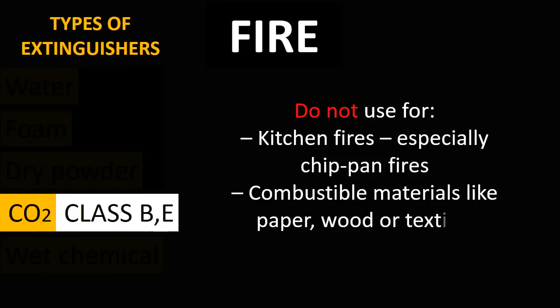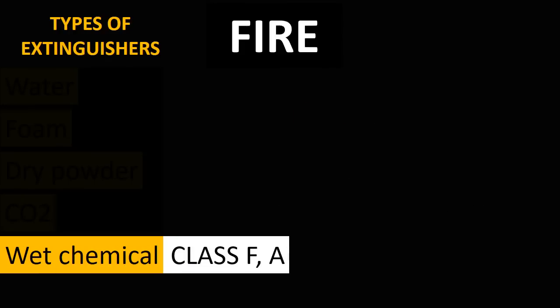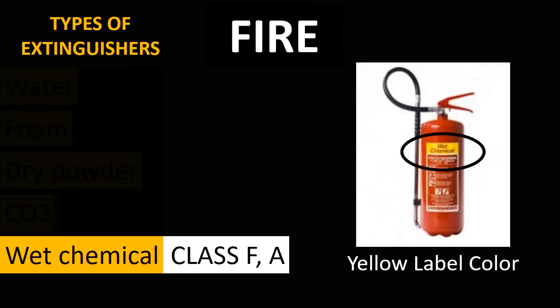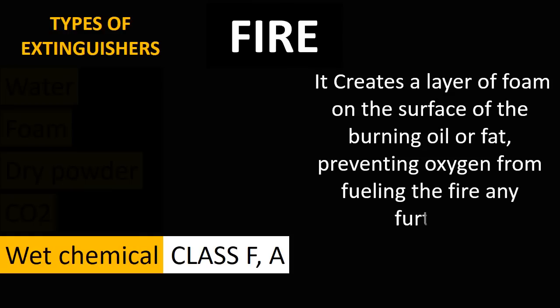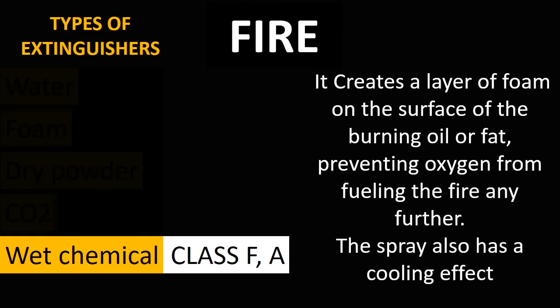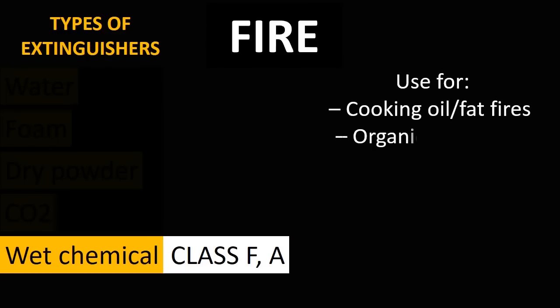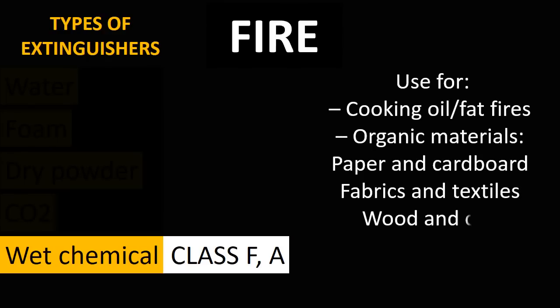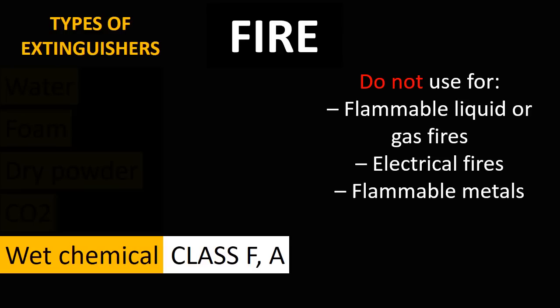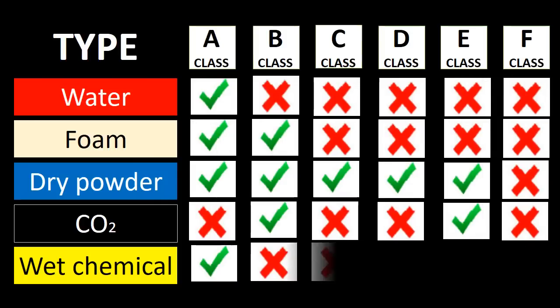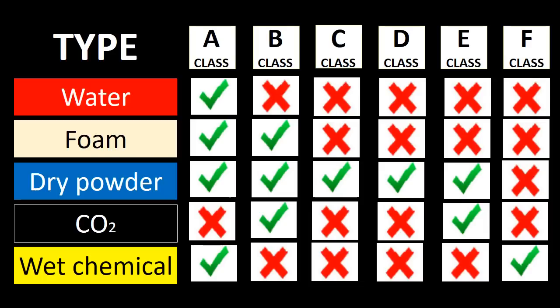The last type of fire extinguisher is wet chemical. Wet chemical type fire extinguishers are used for Class F and Class A fires and they have a yellow label color. Wet chemicals create a layer of foam on the surface of the burning oil or fat, preventing oxygen from fueling the fire further; the spray also has a cooling effect. These are used for cooking oil or fat fires, and on organic materials such as paper, cardboard, fabrics, textiles, wood, and coal. Do not use wet chemical fire extinguishers for flammable liquid or gas fires, electrical fires, or flammable metals. So before you fight the fire, make sure you are using the right type of fire extinguisher for the right class of fire.